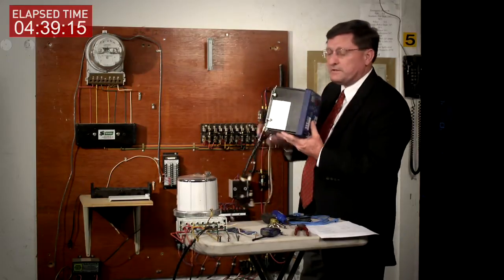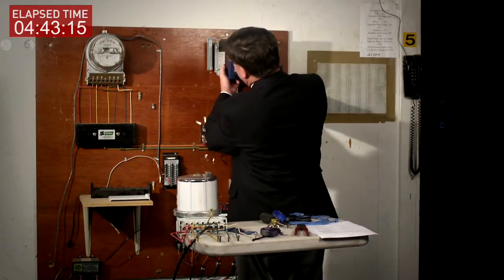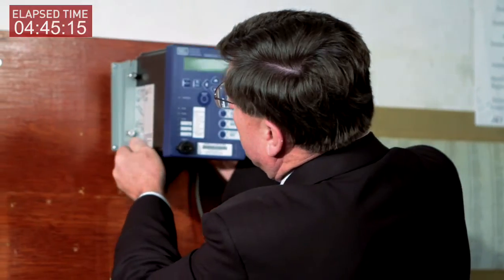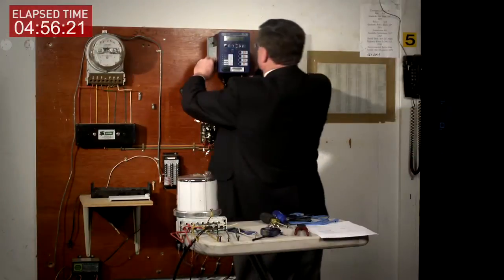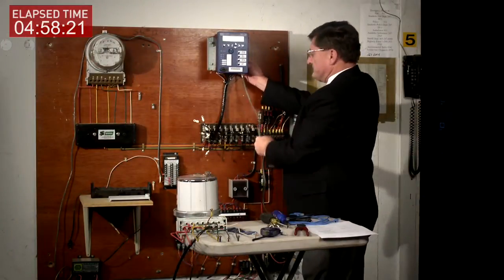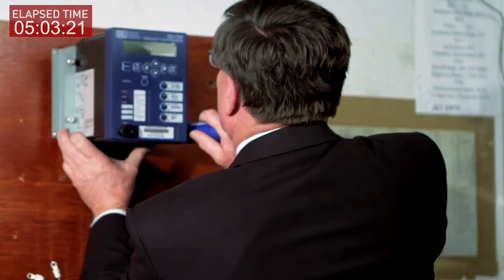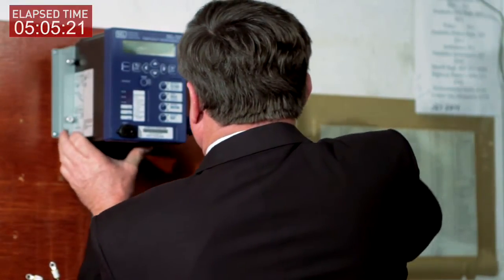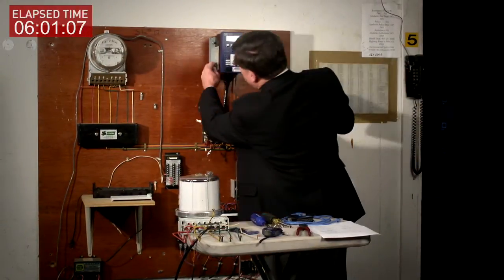Now we're going to simply install our SEL 735 meter. We're going to do this by attaching two mounting screws here. Now we have our SEL 735 attached to the panel. We're going to install two more screws for mounting on the opposite side. Now as you can see, we have our SEL 735 properly mounted on our panel.